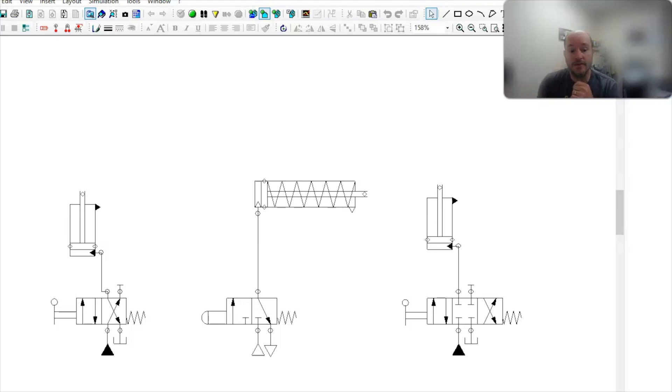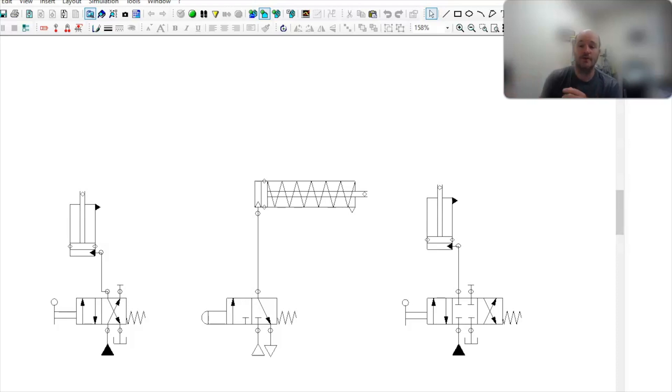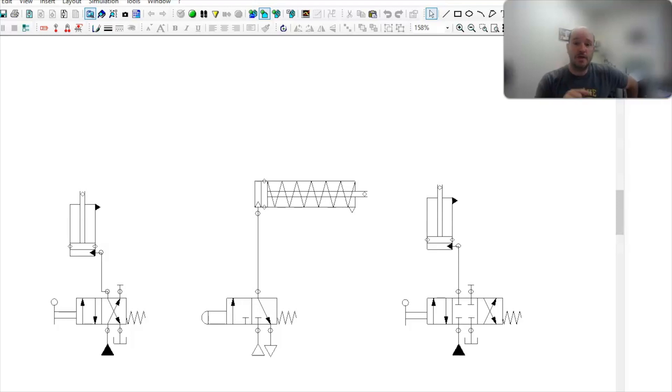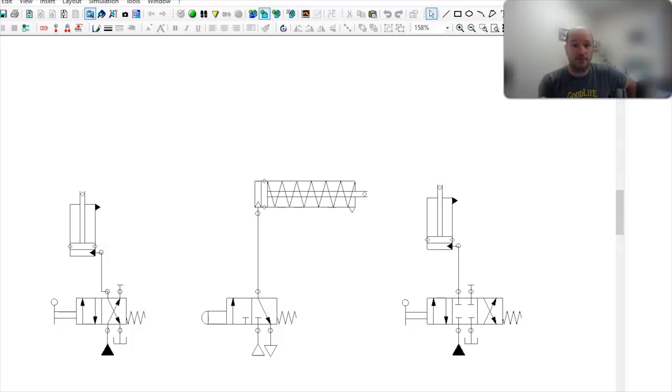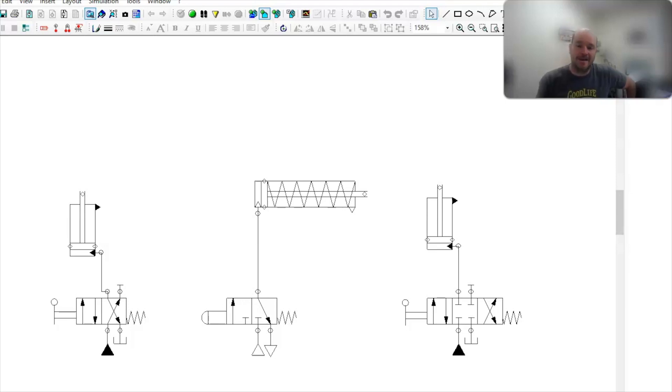But, this is a 4-way directional control valve, but notice that the B port here is plugged. So, it's going to behave like a 3-2 directional control valve. And, they do this on purpose. It is very rare to see a 3-2 directional control valve in hydraulics. It's much cheaper for the manufacturers to just make a bunch of 4-2 directional control valves, and then plug the B port. This is much, much more common. So, that's why this symbol right here, that's the symbol for blocking that.